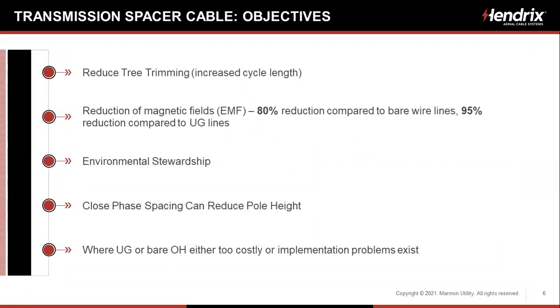We're going to reduce EMF, which is not a big deal here in the US these days, but we're going to get 80% reduction in EMF compared to bare wire lines and up to 95% reduction compared to underground lines. We're going to promote environmental stewardship, and we'll discuss this in a brief moment. And close phase spacing can reduce pole height. And lastly, the other justification or motivation for high voltage covered conductors is where underground or bare overhead is either too costly or you just can't do it. The implementation problems exist, so you're looking for a solution where you have very few options.